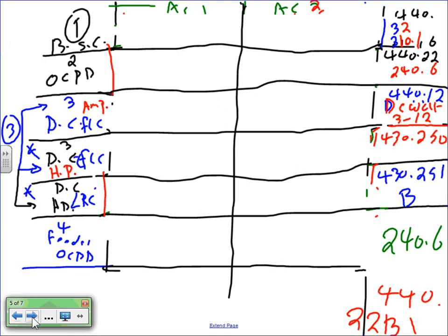All right, let's go to the following, guys. A couple of things that we need to adhere to. So number 1 was my branch circuit. If you guys go to 440.22, 440.32, and this has actually changed slightly, so let me just go directly into here. Let's use red again. 440.32, Chad, right? Yep, .32. And also don't forget the table 310.15(B)(16). These are the rules that you need to apply.